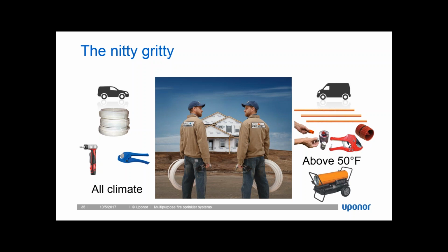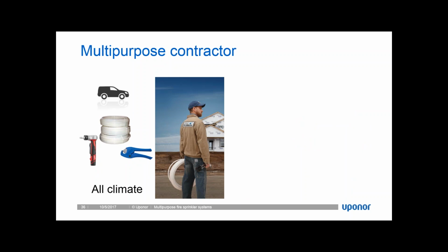Usually heat comes out on the job site when the mud is being installed on the sheetrock. And at that point, it's usually insulated. So this would be heat on the job site before insulation is installed, and I have to maintain 50 degrees. There's going to be a lot of heat leaving that building while that installation is going on. So looking at contractor 1, our multi-purpose contractor, first we're going to experience fuel savings, both in the amount of energy to transport the material, and if I'm doing a winter installation, I don't need to pipe heat to the building.